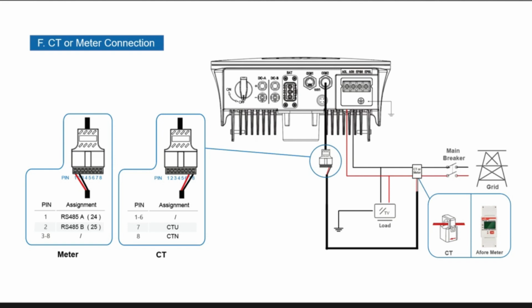Errors that you'll find on the front of the inverter when you first switch it on. Generally, depending on where the inverter's come from and how it's been set, it may have a J01 error, a J07 error, and a B06 error. All that means is you've not set it up correctly on the front of the inverter at the time. J01 and J07 are where the inverter has been set to meters instead of a CT clamp. So you need to go into the settings inside the inverter, change the settings that you want. The B06 might be that the inverter is actually set to no battery or set to the wrong battery.